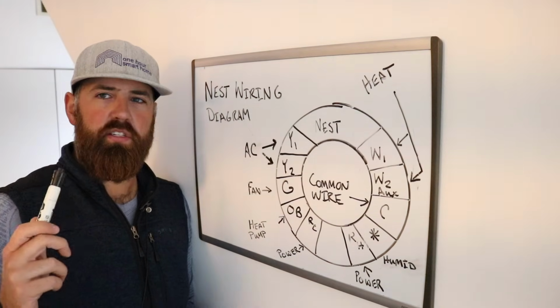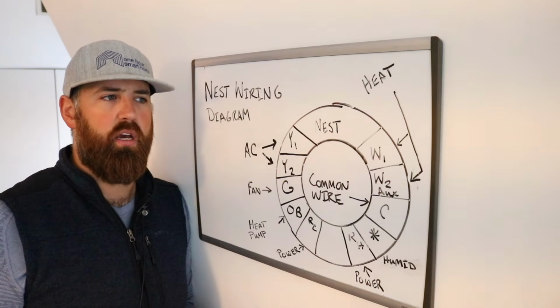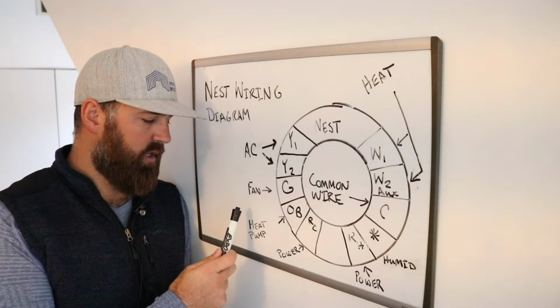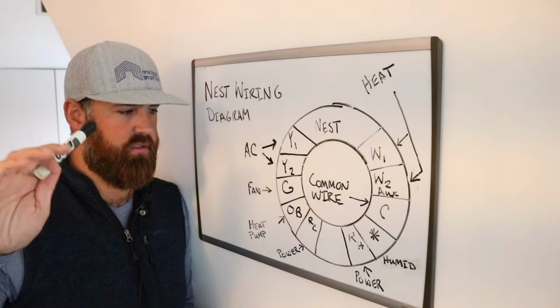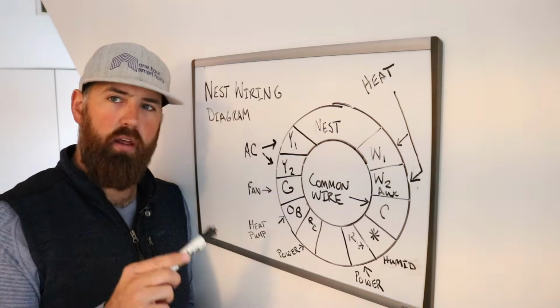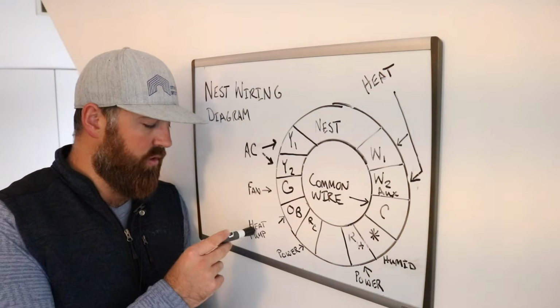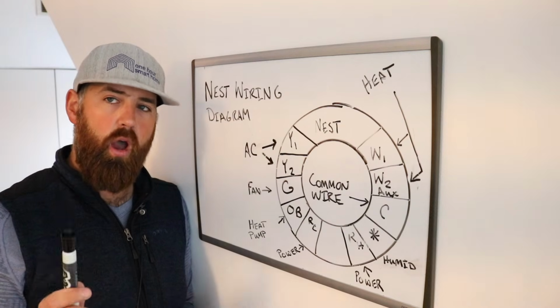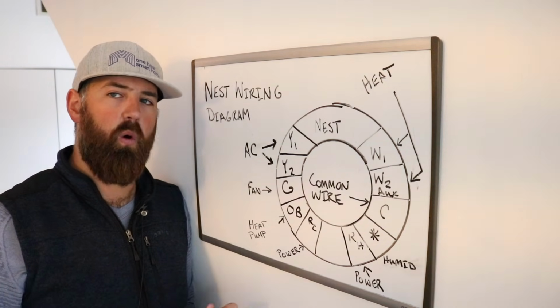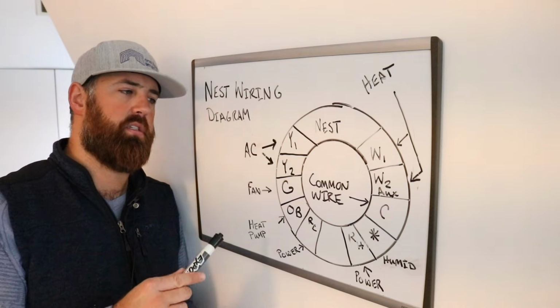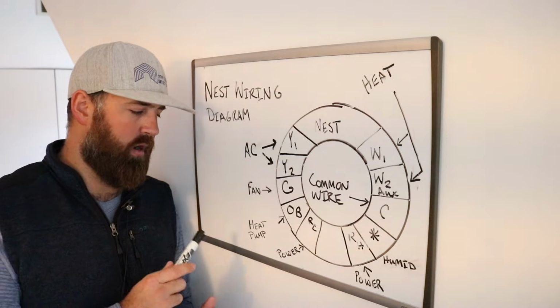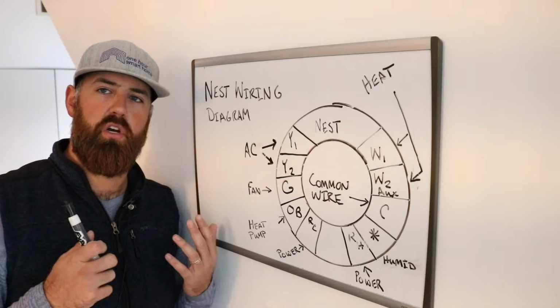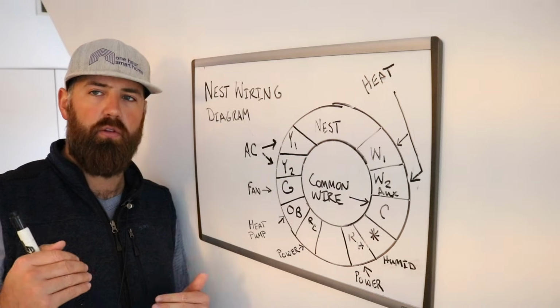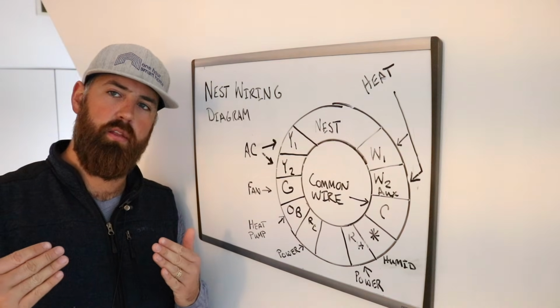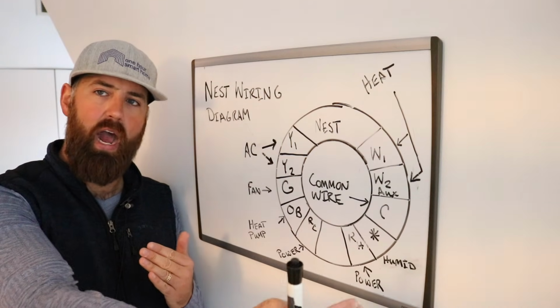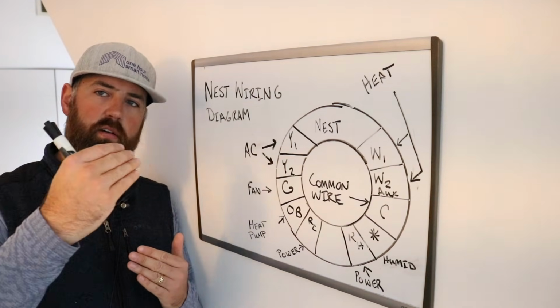The OB terminal: if you live in the upper Midwest or the Northeast, you probably don't have this heat pump. But if you live in the South or a more moderate climate, you're going to have this OB terminal. We're not going too far into heat pumps here since we'll have another video on heat pump wiring for the Nest, because it's very specific how you need to wire it. But basically, the OB controls your heat pump and what's called a reversing valve, which allows your heat pump to either pump heat into your house or remove heat from it.